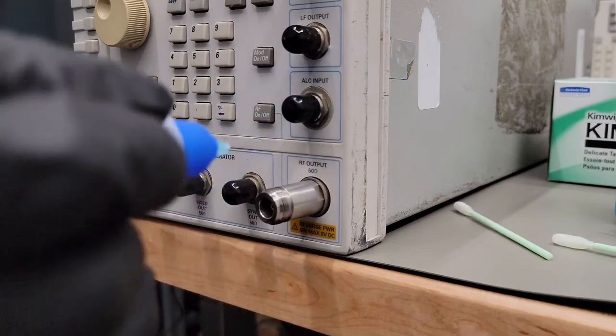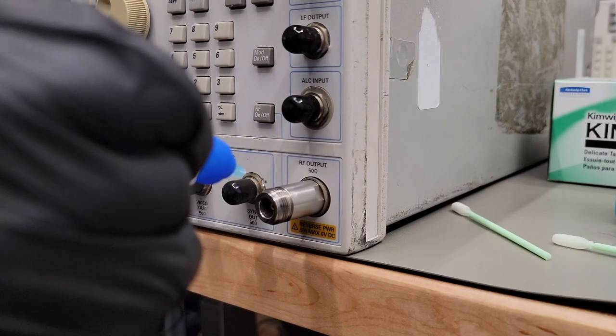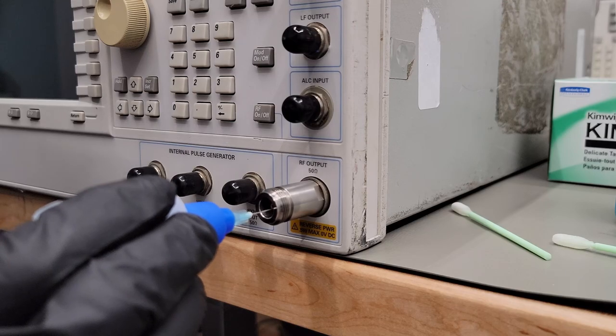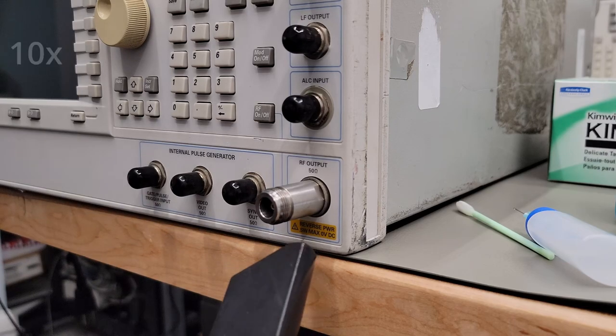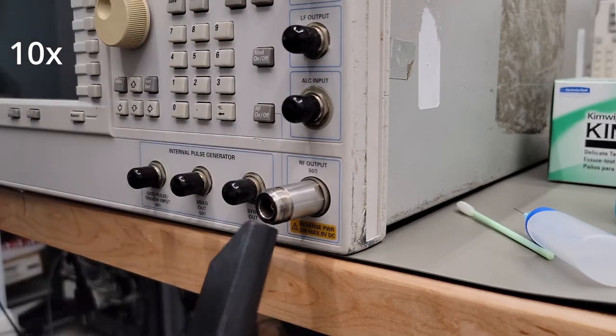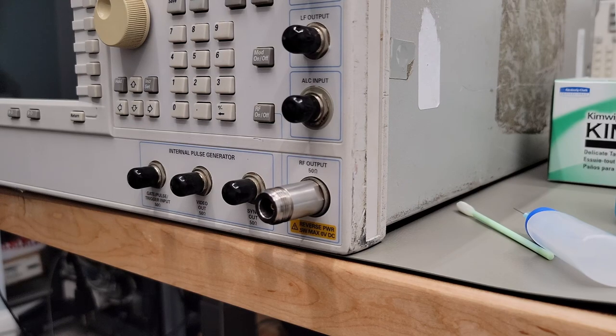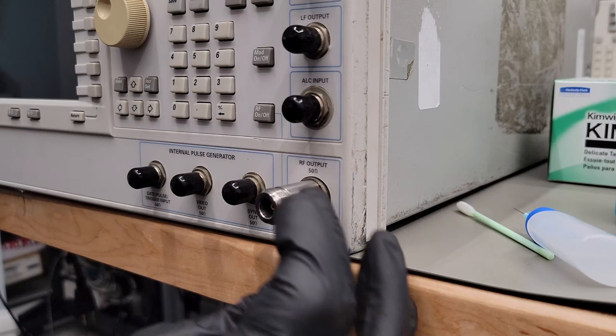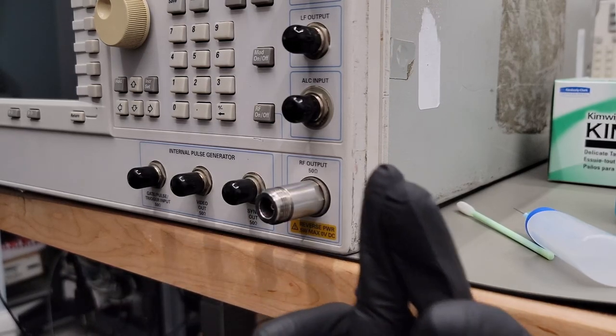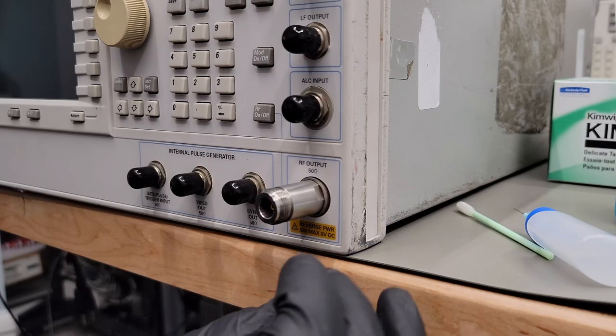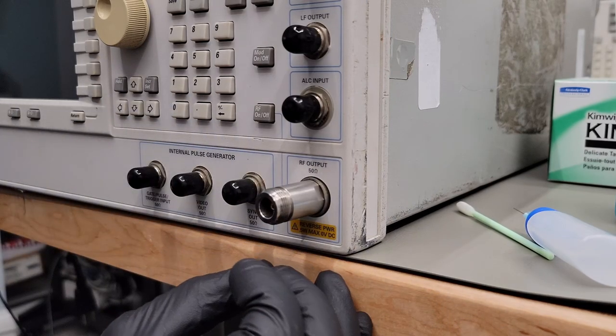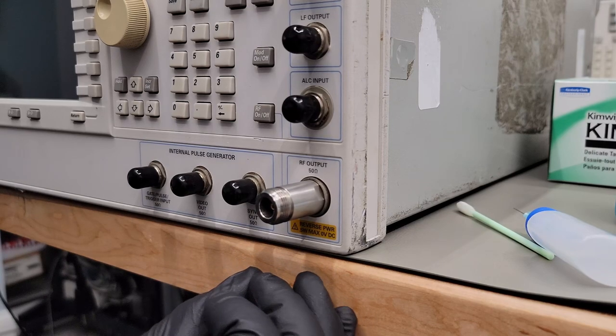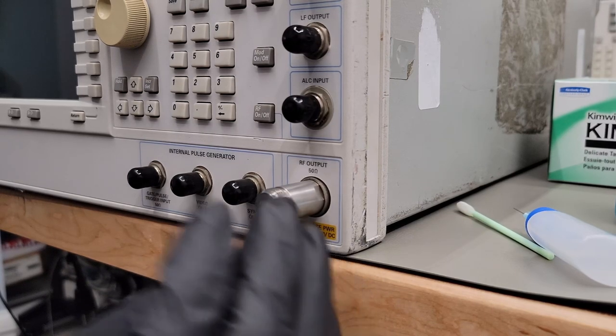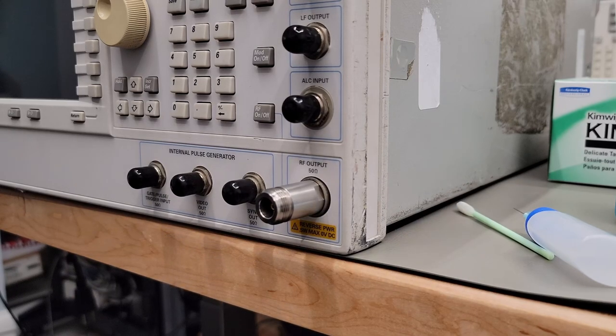And then I'll just apply a little bit more alcohol and do that again. And that's all you really have to do to get a connector like that clean. So now that I'm confident that it's clean, I'll just inspect the threads one more time, because I know this connector was hit at some point and that's why it's bent. I'll inspect the connector again to make sure it's safe to thread on my adapter, and then we'll hook it up to a spec an and see what the output of the signal generator looks like.